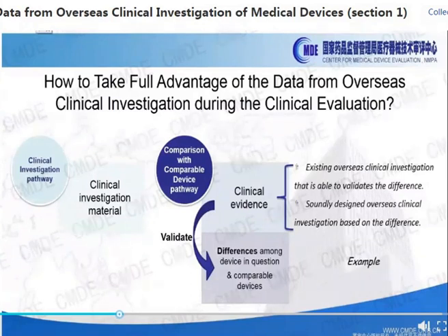And when choosing the comparison with a comparable device pathway, applicants shall conduct a clinical evaluation. Characteristics should be broadly similar between the device in question and the comparable device, but consideration must be given to the impact of the device's differences. Overseas clinical investigation can be used as one possible clinical evidence which demonstrates that the differences among these devices will not bring adverse effect on the product safety, clinical performance, and/or effectiveness.